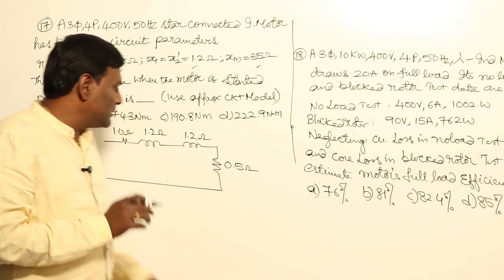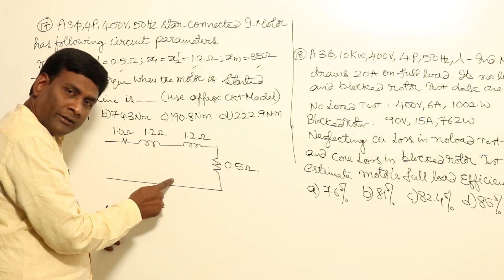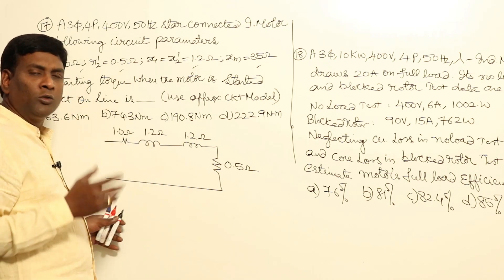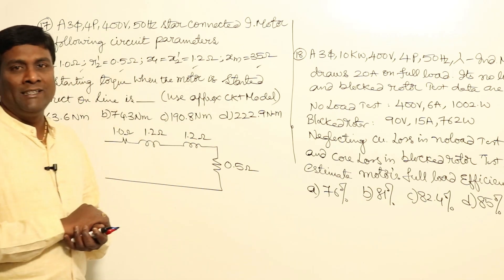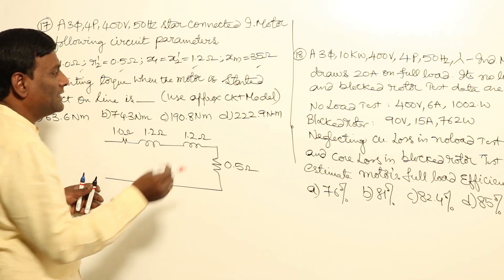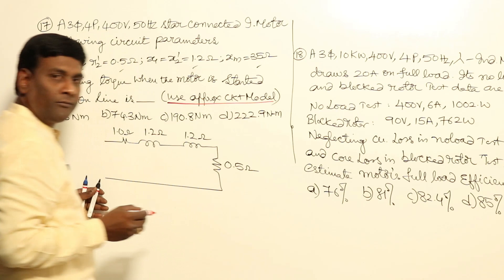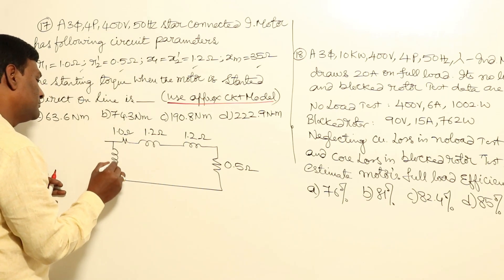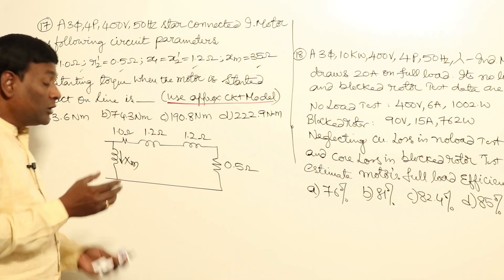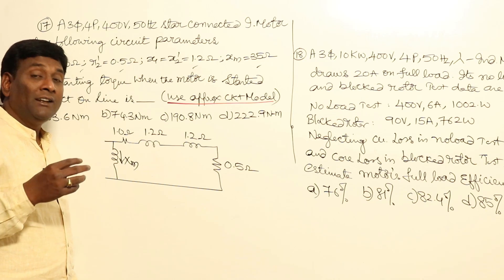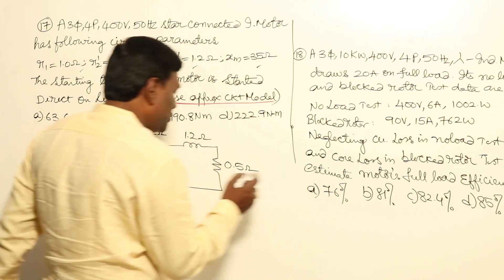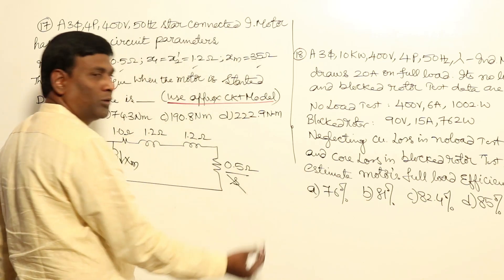In an induction machine, XM is drawn at the input terminals in the approximate model. RC, the core loss component, can be removed. He said to use the approximate model, so XM is kept at the front. Currents flowing through XM develop flux but do not develop torque. At starting, S equals 1, so R2 dash / S equals R2 dash.